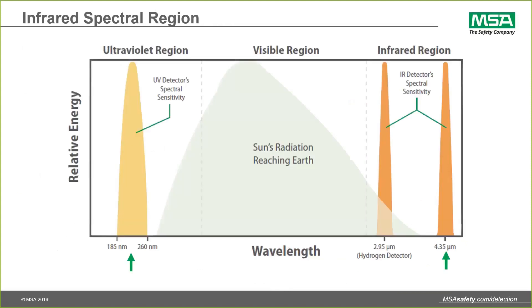This slide shows that optical flame detectors in good working order will not respond to the sun. You can see the sun's radiation reaching the earth. Other than a little bit of intersection on the 2.95 micron frequency — which is tuned out — the detector in good working order will not respond to the sun, because the radiation levels just are insufficient or don't even intersect the spectral sensitivity wavelengths that we're measuring.